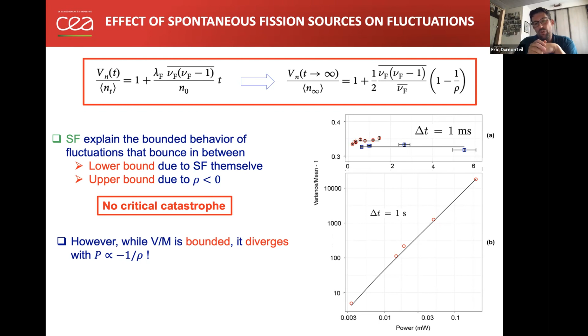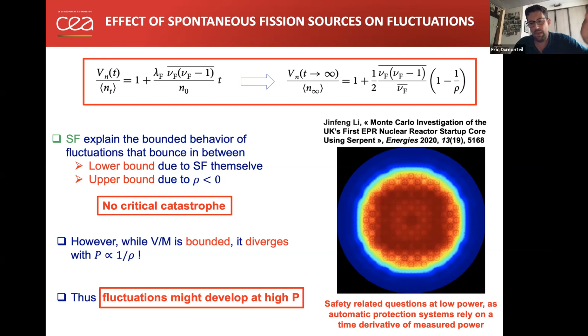So at the end of the day, we have a model that explains very well the observed and the simulated fluctuations, and everything seems to indicate that the fluctuations might very well develop in power reactors at low power, which opens safety-related questions. Why do I say that? It's because the automatic protection systems of power reactors, which are meant to shut down the core if the flux rises too fast, use a measurement that is done from time to time in the reactor. This measurement uses a time derivative of the flux. So if you have too big a noise affecting the flux, it's hard to measure a derivative and to assess if there's an abnormal rise of the flux in the reactor.